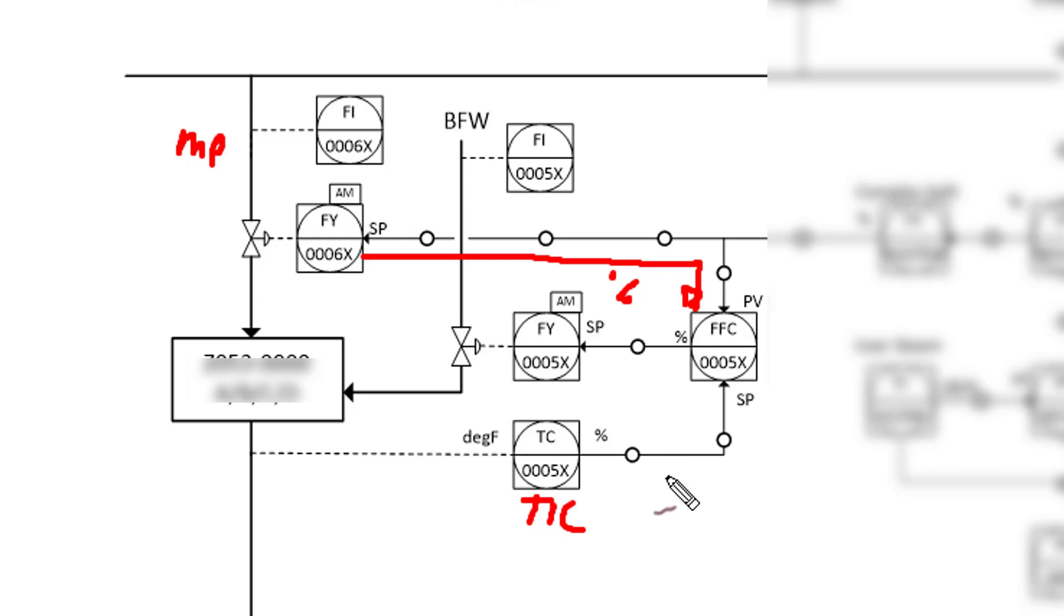Let's draw that in. This is your ratio, which is 0 to 2 for all intents and purposes. We know this one is 0 to 100 percent. So 0 to 100 percent of the valve goes into here, and then we ratio 0 to 2 percent. This could go from 0 to 200, we would clamp that, and it sets the position of that valve. Now these are all linear trims. So if I plot valve lift versus flow, that's linear, and I plot this one as well, and that's linear. Then if you think about it, we've solved the ratio problem.